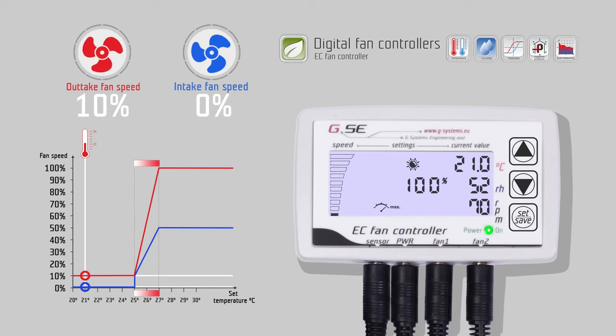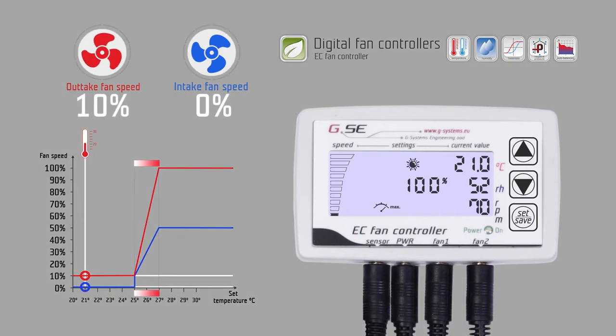These first 6 settings apply throughout daytime. The LED indicates the state of the fans with a constant shining during daytime. During nighttime, the LED is blinking, and the controller uses the next 6 settings, which are set the same way. After you have gone through all of them, press down again to set the negative pressure setting.